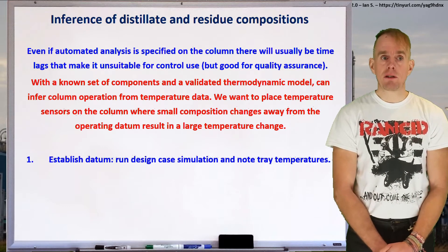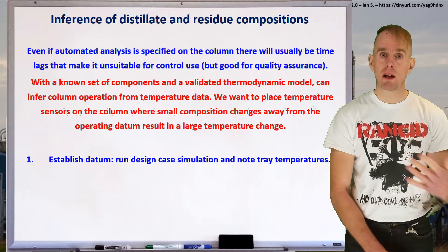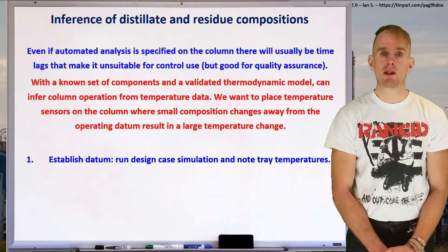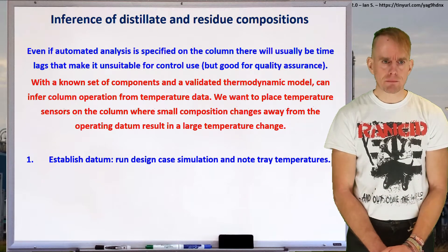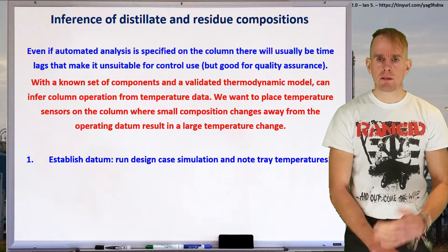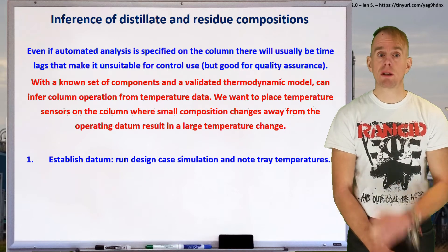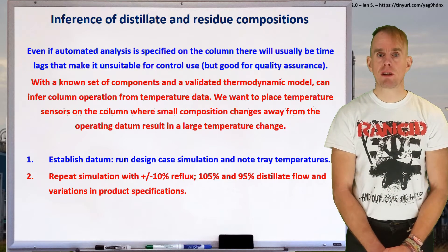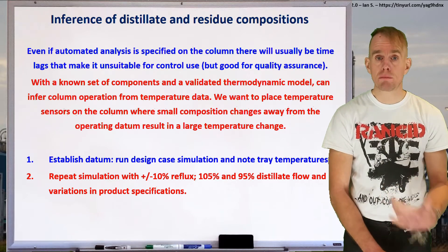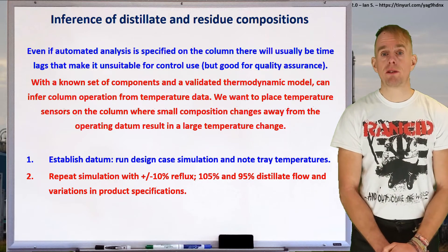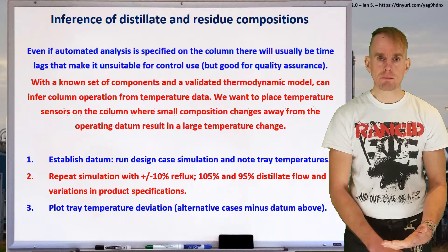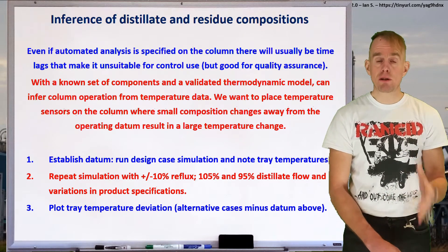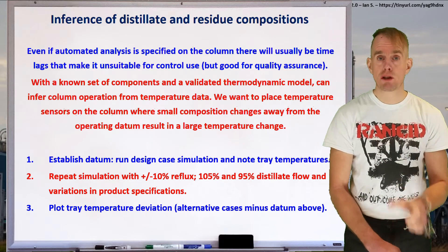Let's establish a workflow. The first thing we're going to do is to figure out what our datum case is. From the last part of this lecture, we've already got a datum for our particular example — we know the number of feeds, stages, feed stage location, feed preheat, and column pressure. For our datum case, we're going to run our simulation again and record the temperature profile of the column, looking at each of the tray temperatures. Then we're going to change things: increase and decrease reflux, change the distillate flow rate, and change our product specifications. For each scenario, we note the temperature profile. With these data, we plot temperature deviation, which means the temperature profile of one of these alternate cases minus the temperature profile of my datum.